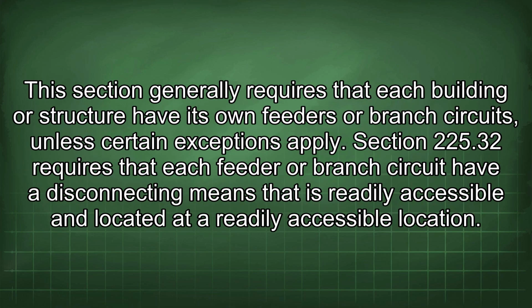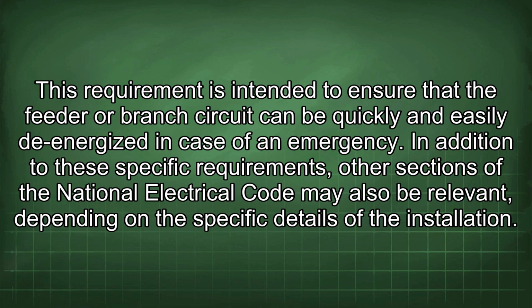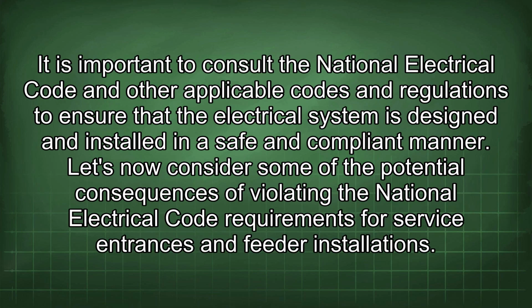This section generally requires that each building or structure have its own feeders or branch circuits, unless certain exceptions apply. Section 225.32 requires that each feeder or branch circuit have a disconnecting means that is readily accessible and located at a readily accessible location. This requirement is intended to ensure that the feeder or branch circuit can be quickly and easily de-energized in case of an emergency. In addition to these specific requirements, other sections of the National Electrical Code may also be relevant, depending on the specific details of the installation. It is important to consult the National Electrical Code and other applicable codes and regulations to ensure that the electrical system is designed and installed in a safe and compliant manner.